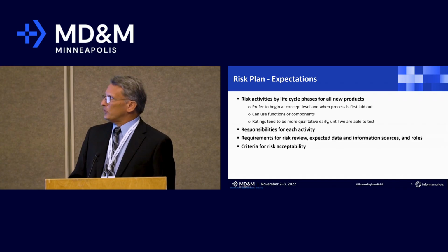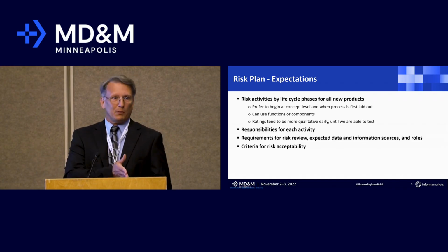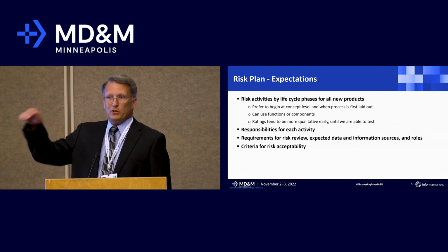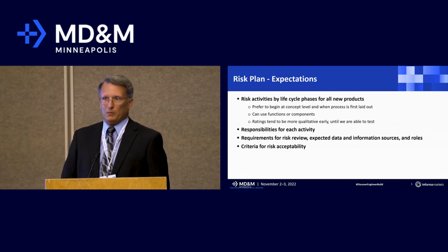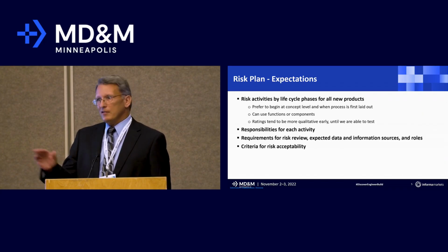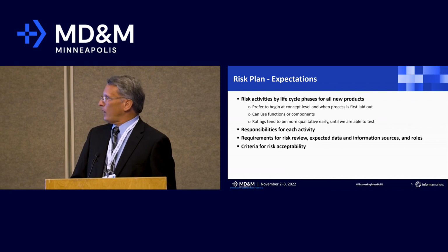And again, the challenge here is the requirements in the risk plan. If you do less than the plan, FDA tends to frown on that. They're going to at least drill in and ask you questions. So if you say the minimum and you dug in because there's a high risk, they're going to be okay with more. But deciding to do less often is a sign that you're behind schedule, not that there is good technical logic for it.